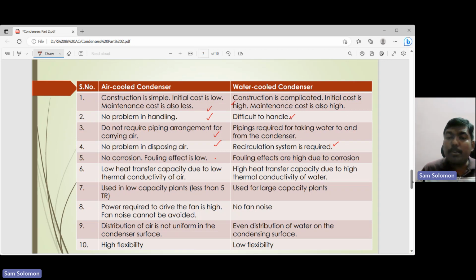So there is going to be no corrosion or fouling effect in case of air. Once again, depending upon the purity of water, you may have fouling effects due to corrosion. Then the disadvantage is that the heat carrying capacity is very low in case of air, and the heat carrying capacity of water is high. Air is used in low capacity plants, whereas the water-cooled condenser can be used for large capacity plants. Power required to drive the fan is high, and so the noise cannot be avoided. Here there is no use for a fan at all, so there is no fan noise. It's a little bit quiet over here.